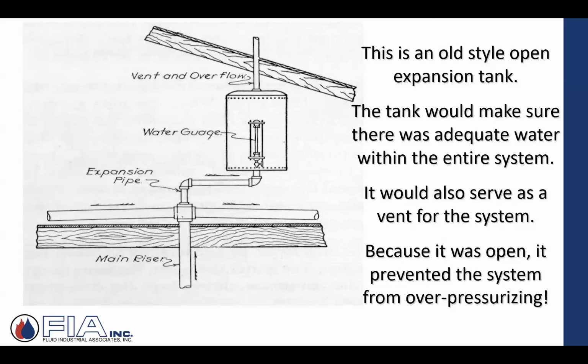To take a quick trip in the Wayback Machine, hydronic systems, when they first came out here, especially here in the Boston area and the East Coast, gravity hot water. So that truly was what they would refer to as an expansion tank. It wasn't closed. It was open to the atmosphere. And its purpose was, as that coal-fired boiler down in the basement truly heated the water and the water expanded, it had a place to expand into without building pressure and either causing a bomb or a relief valve to do its job and relieve pressure. Typically, it wasn't uncommon to have these old tanks up in the rafters, up in an attic, perhaps highest point in the system, with a pipe, an overflow pipe, and a vent, literally penetrating the building, the structure.